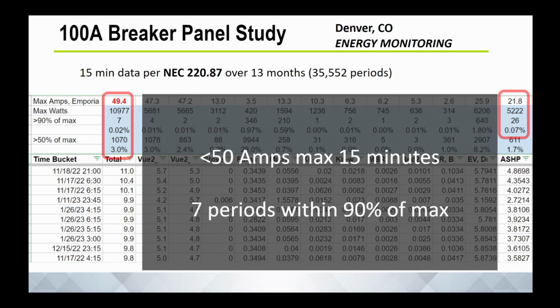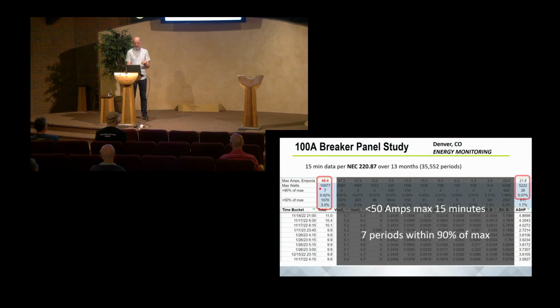It also generates a data set that you can output, and then I started to manipulate it in Excel, in spreadsheets. I basically deduced that after all of that, under 50 amps was my worst 15 minutes. But here's just as important a point: only 7 out of 35,000 fifteen-minute periods over 13 months were within 90% of that peak. And only 3% were within 50% of that peak. This is an exponential curve that is working to our advantage, and I believe this is why we're not going to burn down the houses.